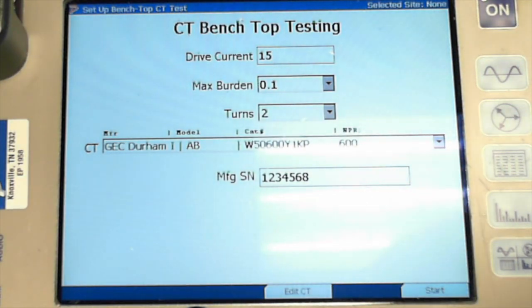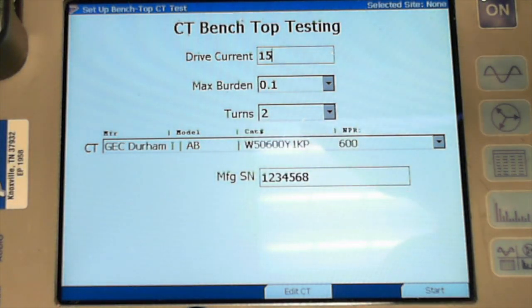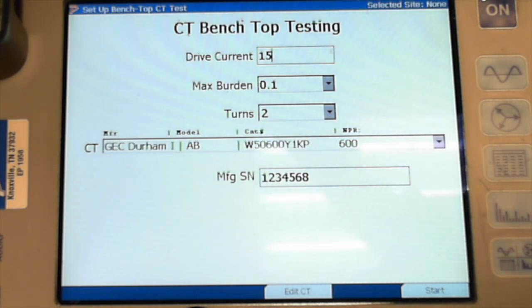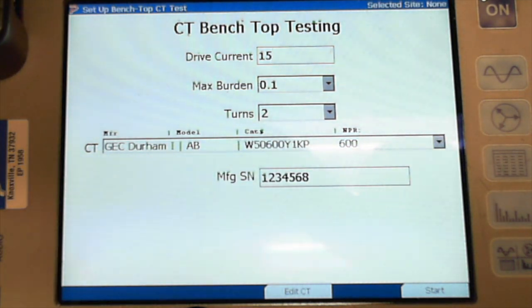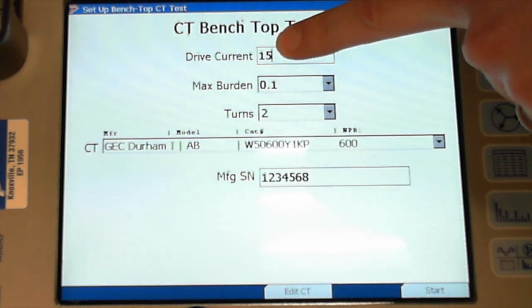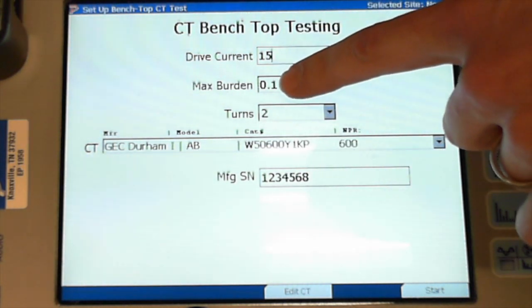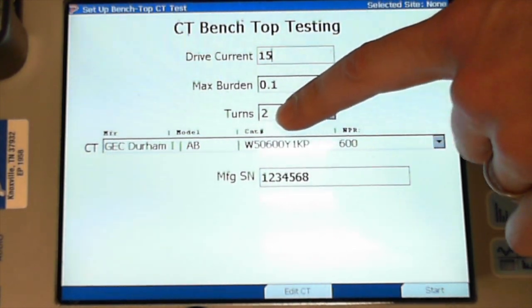So I've got this set up, and I have this PowerMaster, I could drive up to 50 amps one wrap. So let's say, for example, I wrapped it 4 turns, I can go up to 200 amps. But I really want to focus on the lower end, which is where I really think the extended range CT shines. So I'm going to drive 15 amps, adding about 0.1 burden, and then with 2 turns.